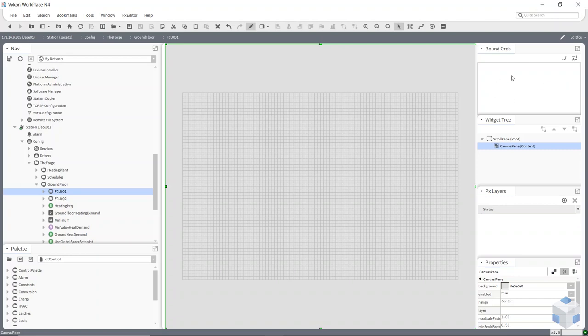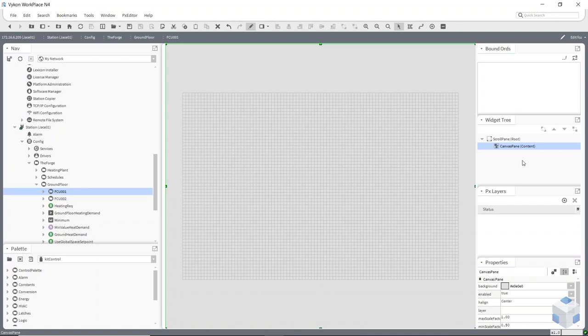Look at these areas here. This is the Bound Ords area — any point I bring onto my canvas will be listed here, but only once. So I could bring the same point on many times and it would just be one ord listed. This is the widget tree: if I brought the same point on ten times, you'd see it only once in Bound Ords but ten widgets in the widget tree.